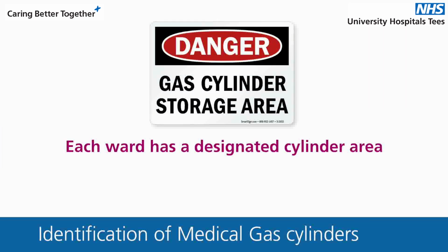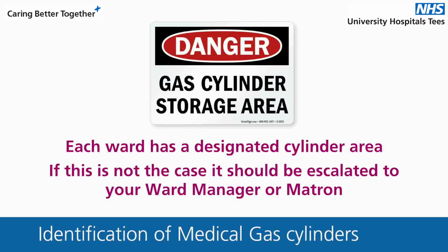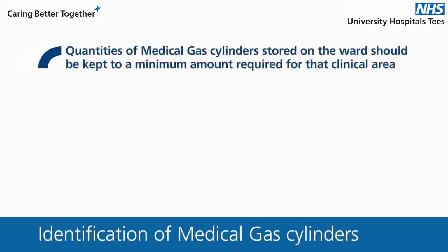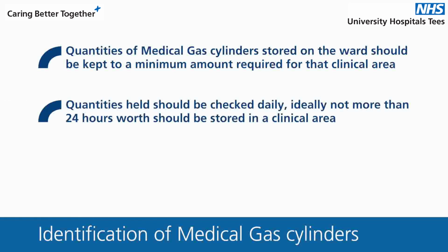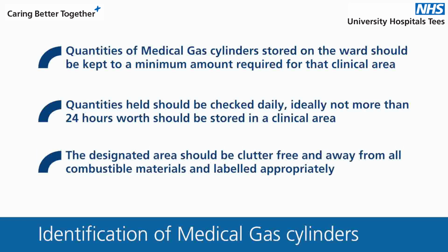Each ward has a designated cylinder area. If this is not the case, it should be escalated to your ward manager or matron. The quantities of the medical gas cylinders stored on wards should be kept to a minimum amount required for that clinical area. The quantities held should be checked daily. Ideally, not more than 24 hours worth should be stored in a clinical area. The designated area should be clutter-free and away from all combustible materials and labelled with the appropriate warning signs.